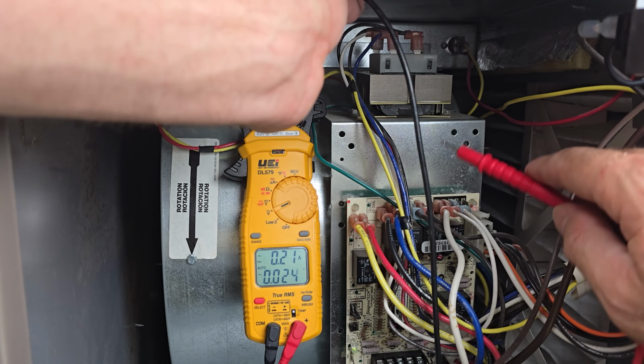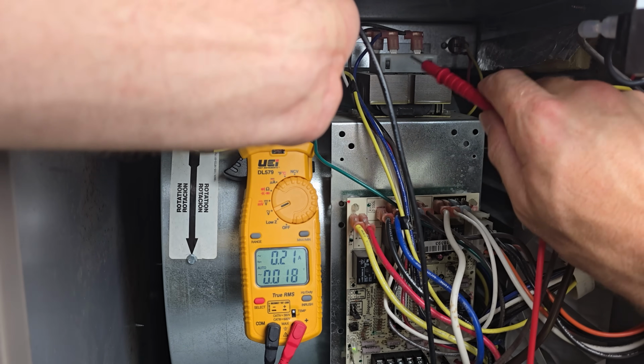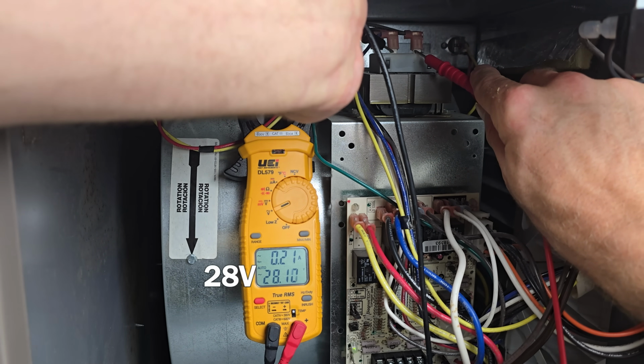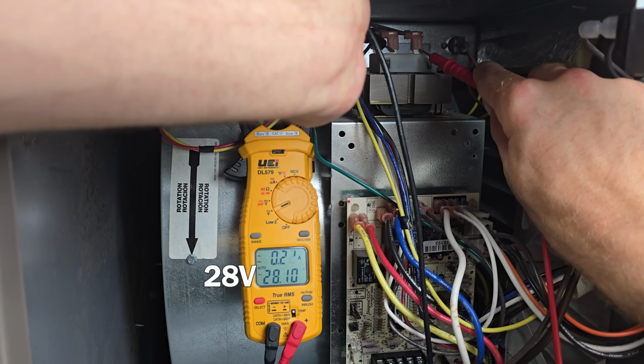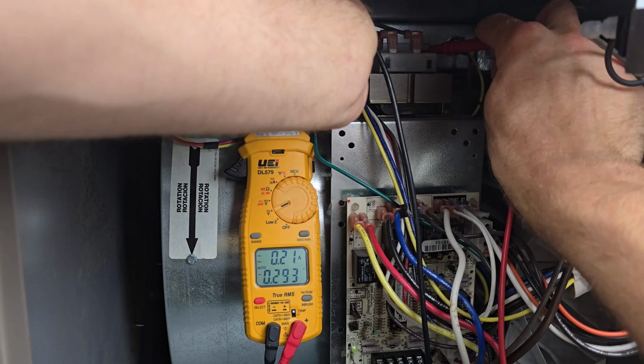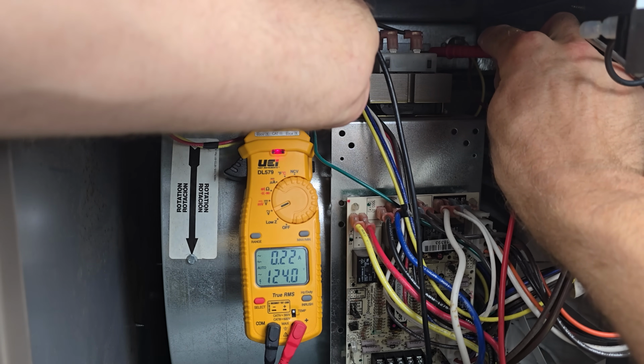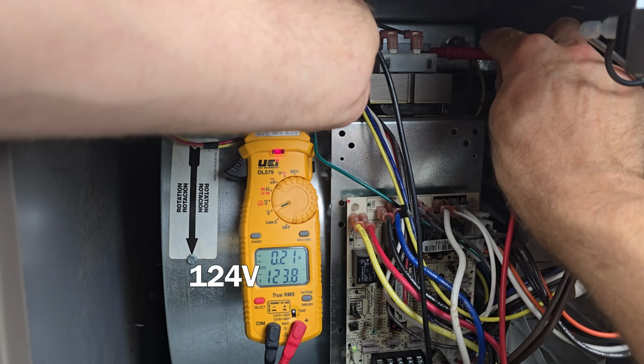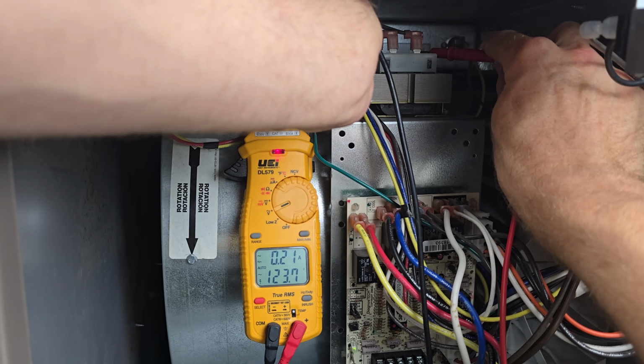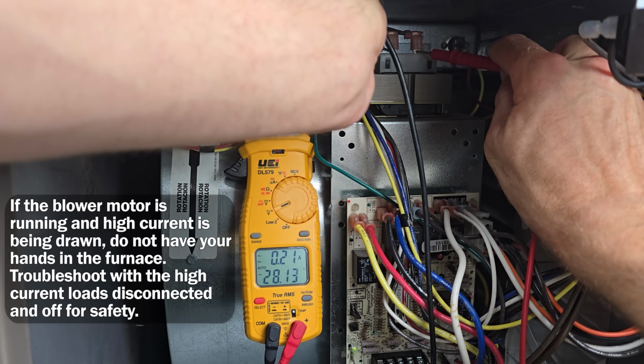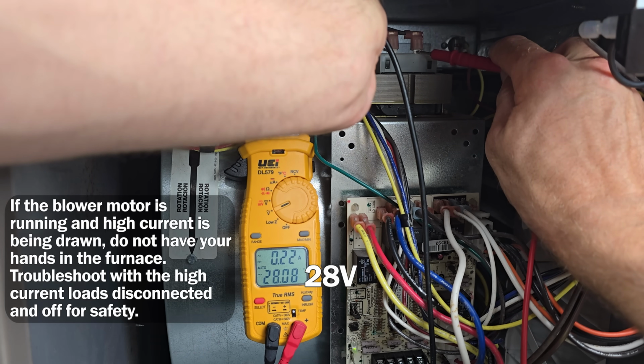So if you have voltage there, but you don't have a status code light, you know, the light is not being lit, you want to check for 24 volt power. So up here on the transformer, we're going to check the taps right here, and you see we have 28 volts. If you didn't have 28 volts, you can measure back here and see, do I have the high voltage power coming into this transformer? So right here, you see we have 124 volts. So if you had 124 volts here, but you did not have your, say, 24 volts, which is actually 28 volts, if you did not have that here, then that would mean that your transformer is bad.